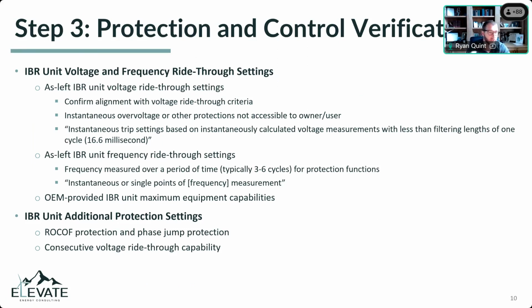But we believe you really should be validating that, verifying that with a simulation to prove that, for a ride-through curve at the point of measurement, the settings that I have at the turbines are adequate or suitable to ride through. But then there's all the other clauses, right? Instantaneous over voltage, and what the trip settings on those types of things are. There are the instantaneous trip settings based on instantaneously calculated voltage measurements with a filter length less than 1 cycle. These are the gotchas that often, again, require OEM engagement, because you're not going to typically find in their documentation, well, what's your filtering for your voltage measurements used in protection? So we usually have to ask these types of questions.